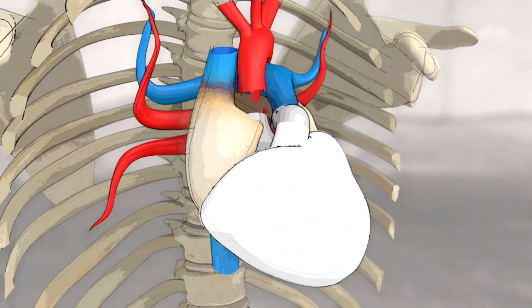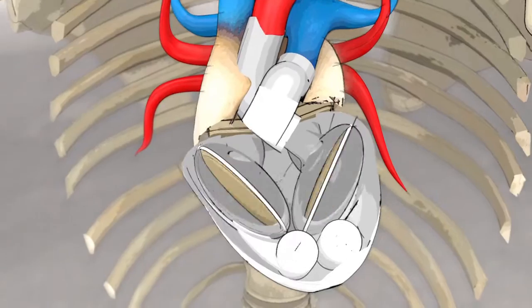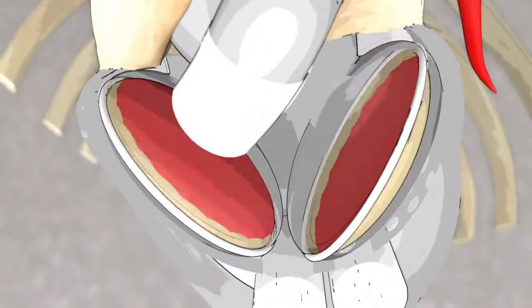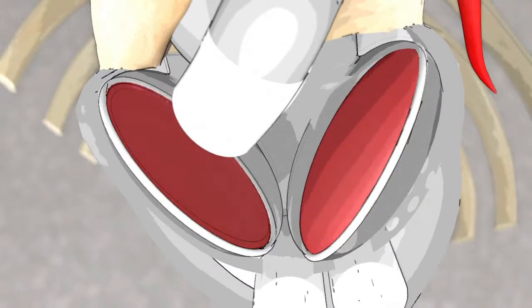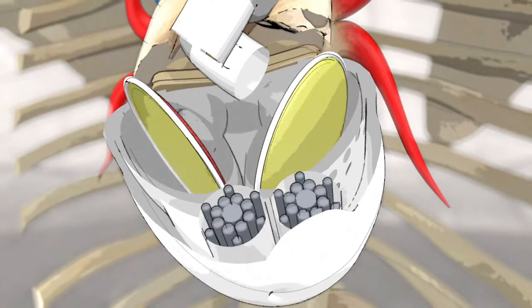clips onto this interface. Both ventricular cavities are divided into two parts, each separated by a double-sided biomembrane. The left membrane, for the blood, is made of cow heart tissue and is treated to avoid the body rejecting it. The other, for the actioning fluid and motor pumps, is made of polyurethane.